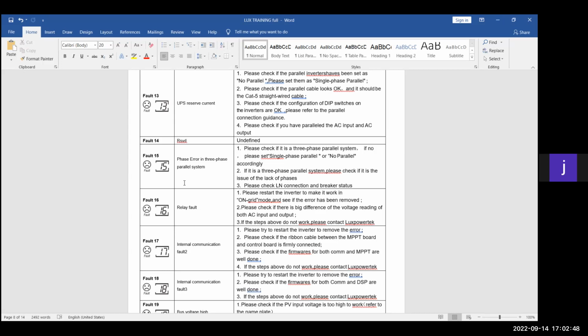So you go to the parallel settings and you say this one that was R phase is now S phase, and that one is T phase. Just swap your phases around on your machines, and then your machines will be happy, or you can physically change the phases as you like. But that just tells you, you said this is phase 1, but it's detecting that it's actually another phase from Eskom. That's why it's giving you this error. You'll get that in parallel systems quite a lot. Then let's go on from here.